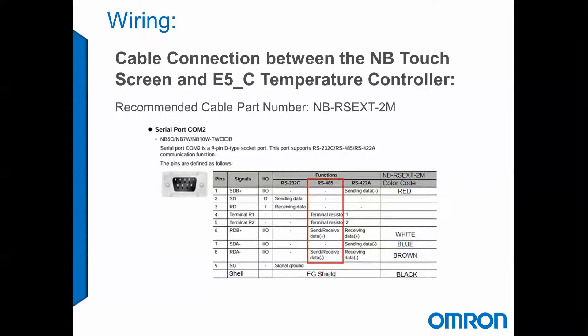The recommended cable part number is the NB-RSEXT-2M. This is going to be a 2 meter cable. One end of the cable will have a DB9 connection, the other end will be flying leads. The main pins we're going to be looking at are pin 6, which is our RDB+, that's going to be our white wire, and pin 8, which is our RDA-, that will be our brown wire.